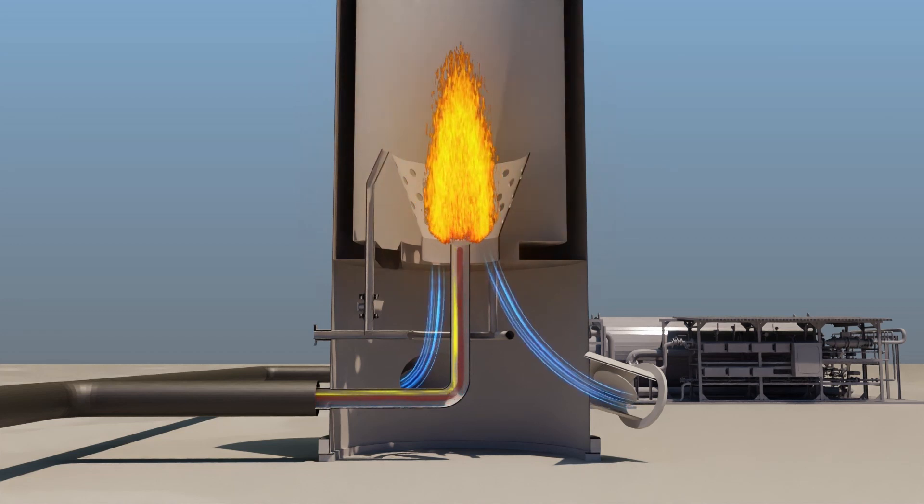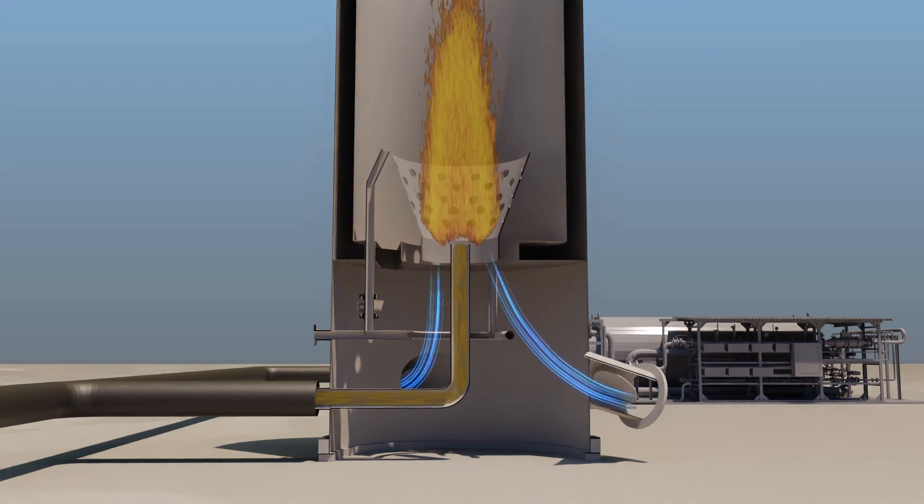To prevent this dangerous scenario, inert gases like nitrogen are added to the vapors to maintain a certain minimum flow rate and thus the specified safe outflow velocity.